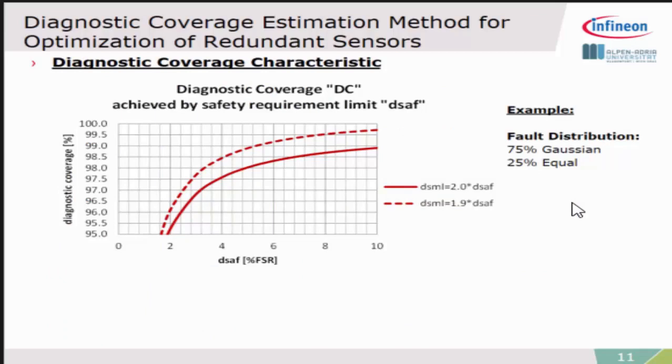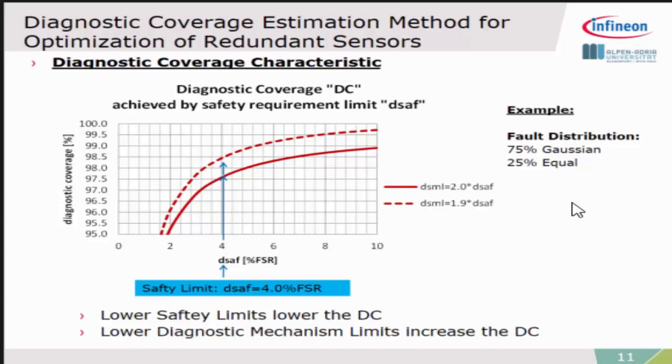These worst case points can be used for the calculation later on. When we draw everything in another graph, where on the x-axis you have the safety requirement, here is the graph of the possible diagnostic coverage figures which you get. In this example from before, if you take 4% of safety requirement, in that case taking 2 times the safety requirement, we achieve 97.5% diagnostic coverage. We can change this by changing the mechanism limit. The lower the safety limit, the lower is the diagnostic coverage, but the lower the diagnostic mechanism limit, I can increase diagnostic coverage. I can optimize the diagnostic coverage which I need. This actually is what we did with our system. We told our customer where to set this diagnostic mechanism limit to achieve the required diagnostic coverage.